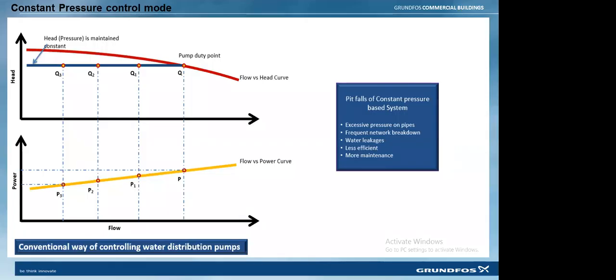Normally in our hydropneumatic system, we use a term called constant pressure. Why do we have hydropneumatics? To get constant pressure on the utility side. That is the answer we give to everyone. But what is the disadvantage of constant pressure? You get excess pressure in the pipeline. With excess pressure, there could be leakages, and pipe breakages can happen. Because of excess pressure, energy consumption also increases, and it creates more maintenance.